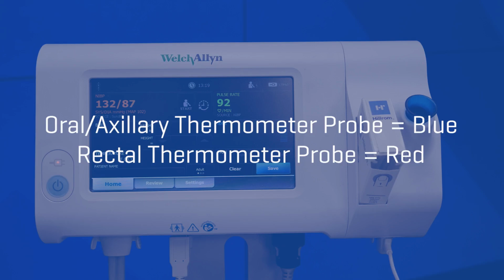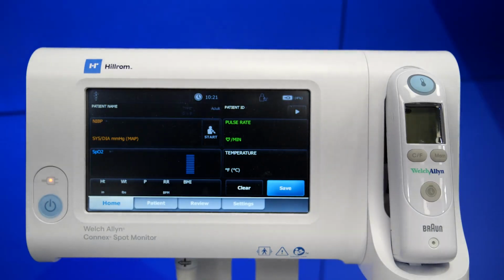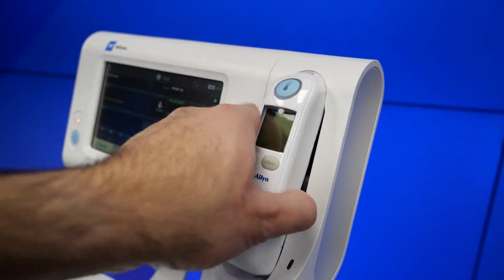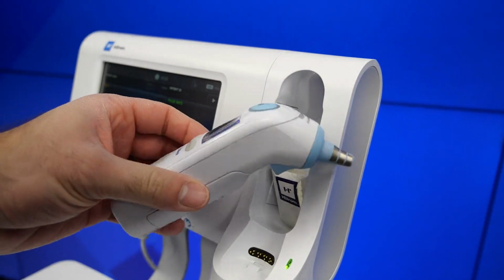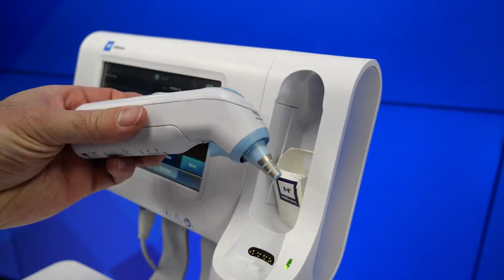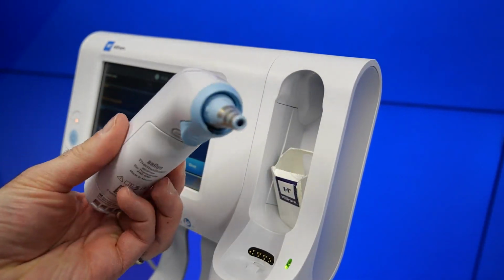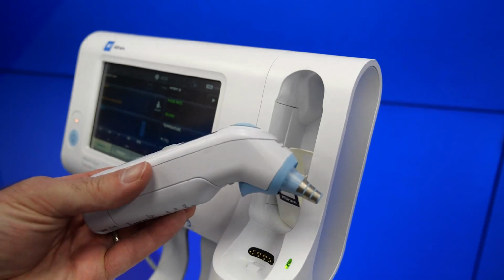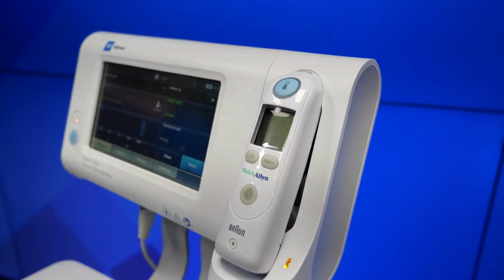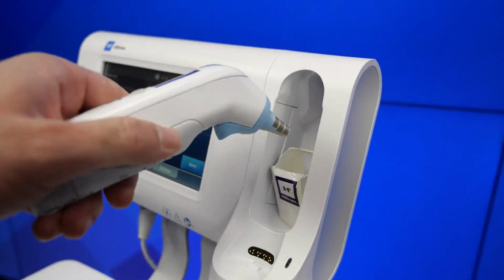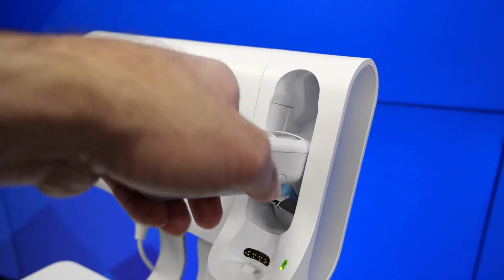Red is for rectal. The Connex Spot Monitor also offers tympanic measurement capability if the unit is purchased with an integrated Braun Pro 6000 ear thermometer. To take a measurement, begin by removing the ear thermometer from the dock and attaching a probe cover. Wait for the ready beep and 3 dashes to appear on the thermometer display. Fit the probe snugly into the ear canal and then push and release the measure button.